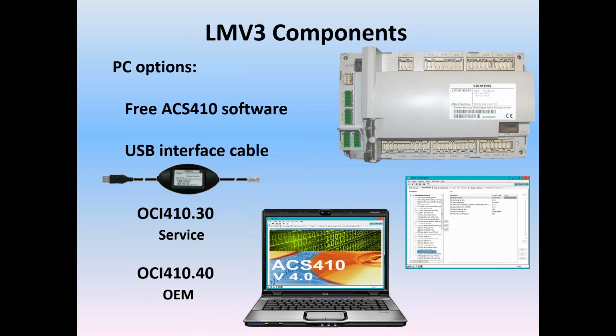Or the OCI410.40 is the OEM version, which will give you settings like flame failure response time and OEM specific settings. All of the OEM settings, and the service settings, of course, can be reached through the AZL display. But if you'd like to commission through the PC, you can.